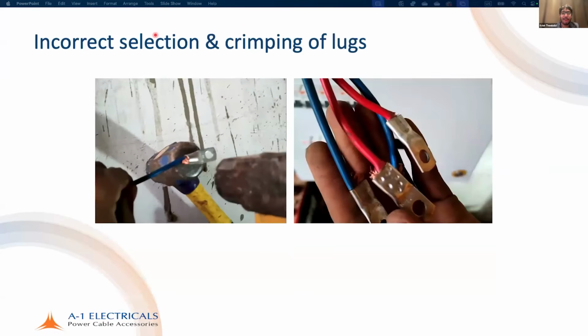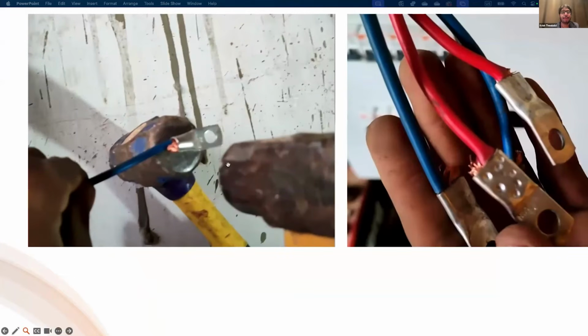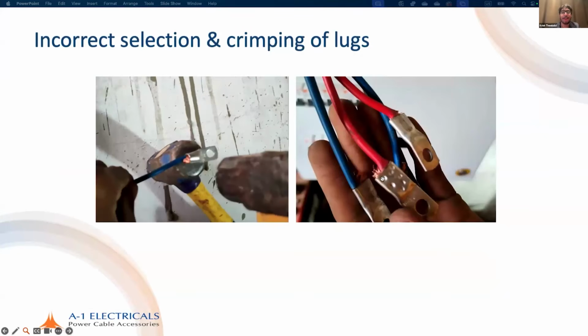Why is this important? Well, we know that in India, most times there are no lugs that are used, and where they are used, they are often crimped, or I would not even use the word crimped, terminated in highly inadequate ways. There was another YouTube video that I was seeing where a guy asked a question: for a 6 square mm cable, what is the correct size of lug? I was thinking, what a ridiculous question. Obviously, it's 6 square millimeters. But he meant that you have to double up the conductor and smash it because it will get so badly deformed. So the correct answer was 25 square mm. And the guy gave away some Vivo mobile phone to the person that correctly guessed the answer.